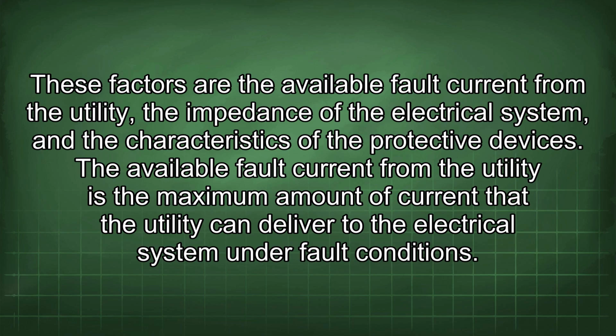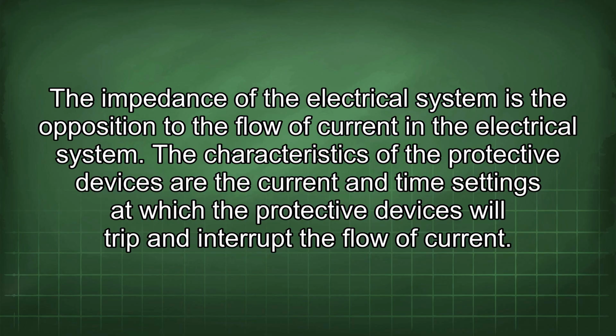These factors are the available fault current from the utility, the impedance of the electrical system, and the characteristics of the protective devices. The available fault current from the utility is the maximum amount of current that the utility can deliver to the electrical system under fault conditions. The impedance of the electrical system is the opposition to the flow of current in the electrical system. The characteristics of the protective devices are the current and time settings at which the protective devices will trip and interrupt the flow of current.